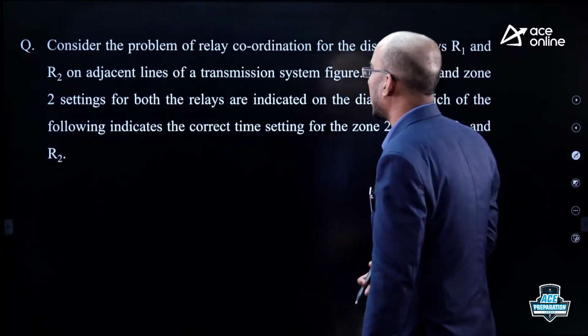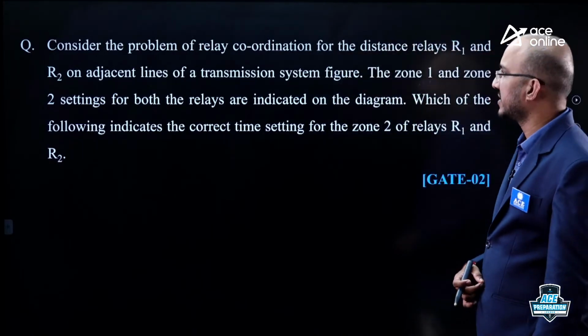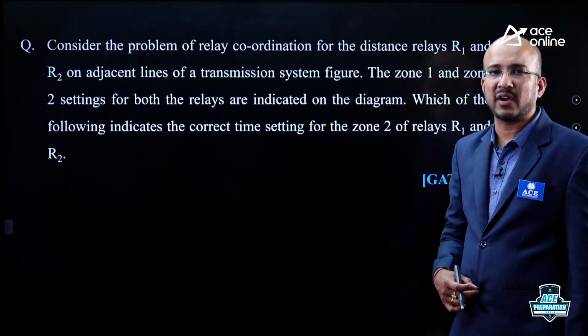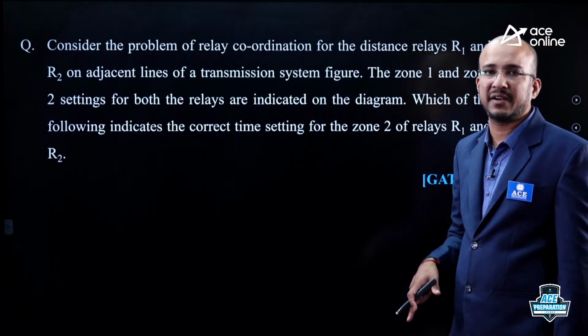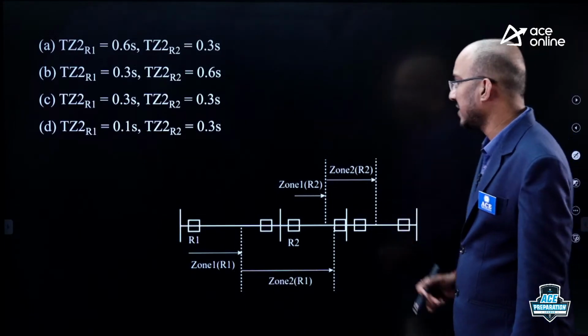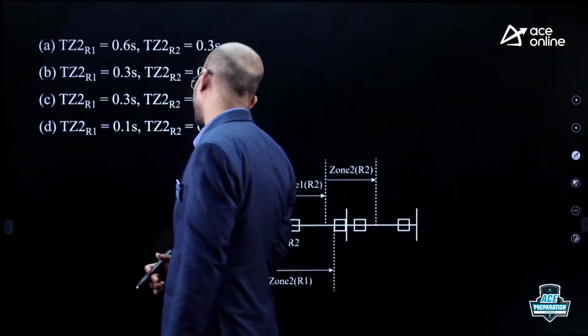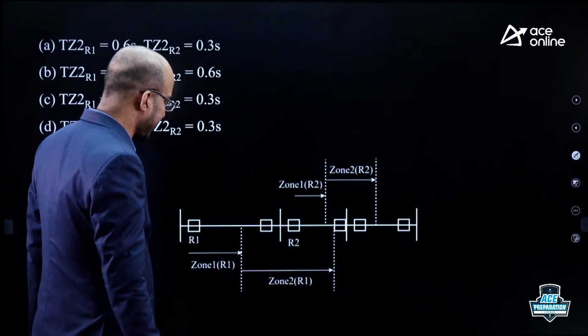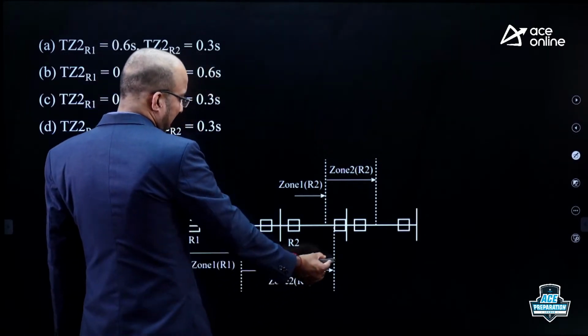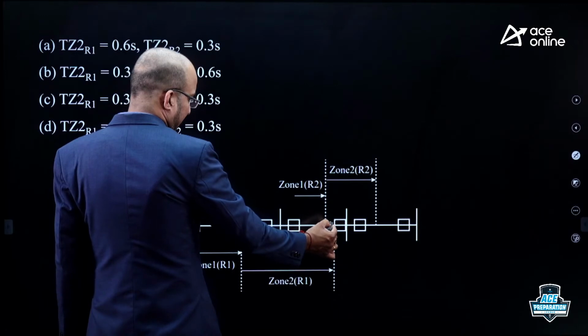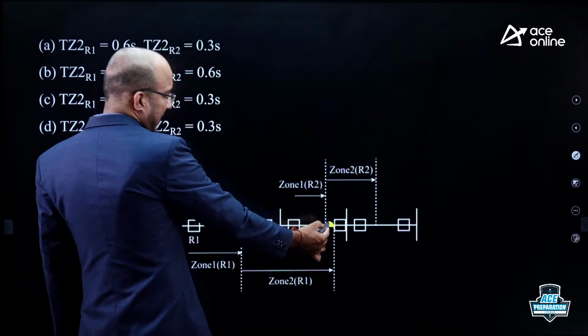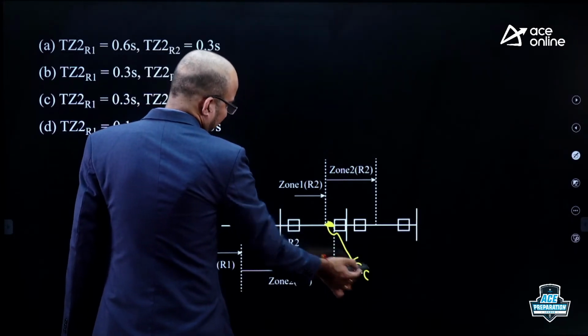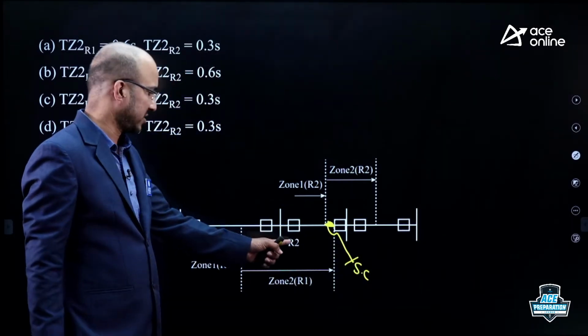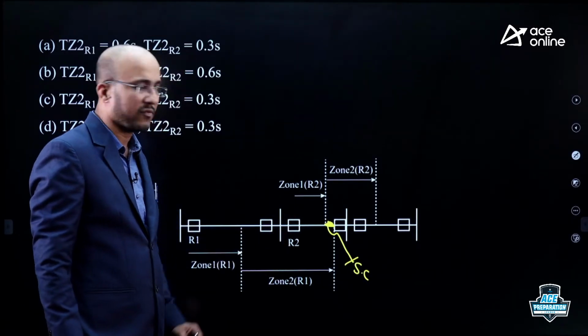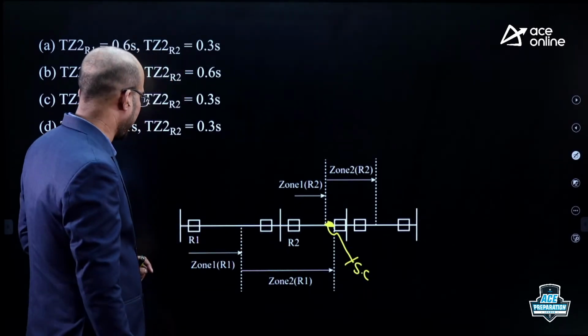Now here, this problem was given based on relay coordination. He is saying that we need to identify the timings of relay 1 and relay 2 in zone 2. He has given this diagram and is asking to identify the timing. Simple logic here: there is an overlap area between zone 2 of R1 as well as zone 2 of R2. So in this area, if there is a short circuit fault, the R2 relay has to operate first because it is in the section of R2.